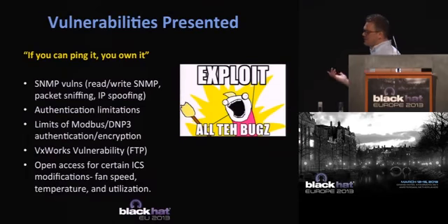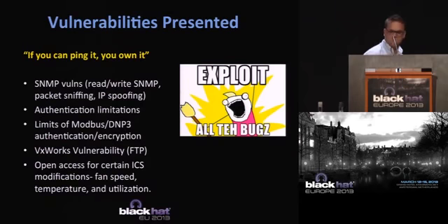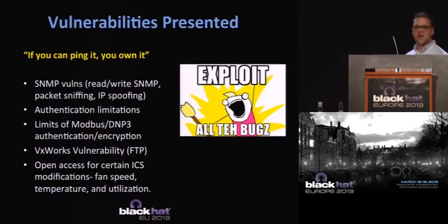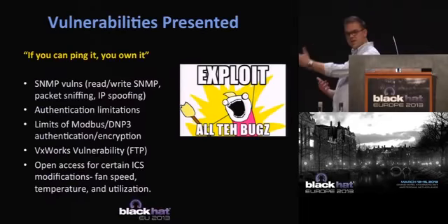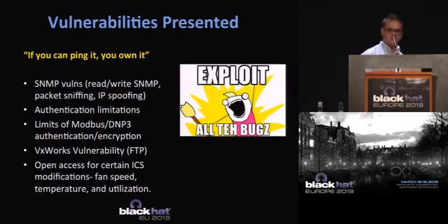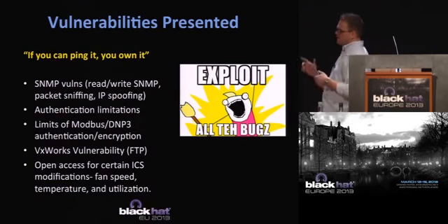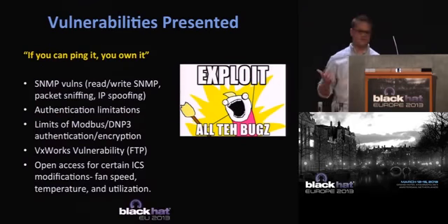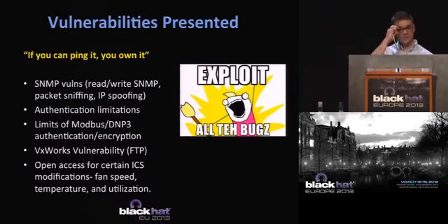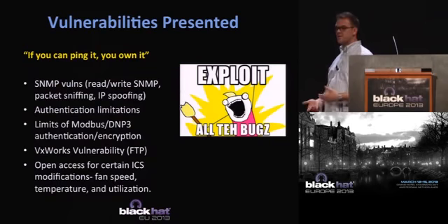I also presented limits of Modbus and DNP3 authentication and encryption. If you remember back to earlier slides, DNP3 and Modbus don't have authentication. They don't have encryption. There are iterations, again, that support those technologies, but in this case, it's not supported. So it's vulnerable to spoofing, it's vulnerable to sniffing the actual traffic, etc. I also presented a VxWorks vulnerability, which is utilizing just FTP, wide open on that, and then I also configured default usernames, passwords, etc. And then open access for certain ICS modifications. So in this case, it would have been fan speed, temperature, utilization, and containment of the water system.